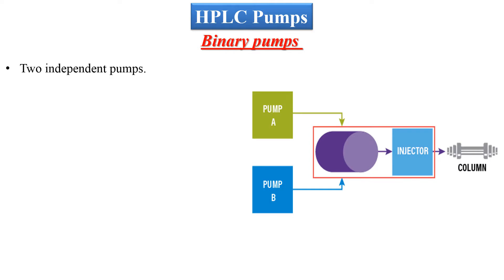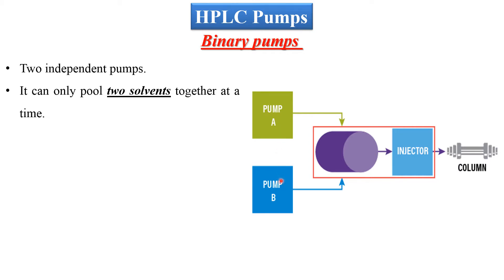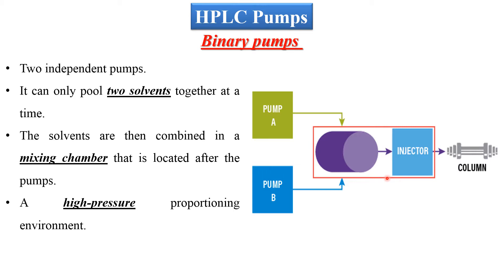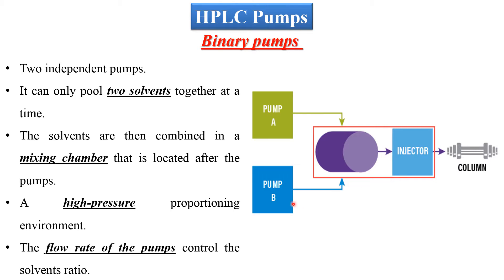As we can see in the design of this binary pump, there are two independent pumps, so it can only deliver two solvents at a time. The solvents are mixed in the mixing chamber before being injected into the column. We can consider this design a high pressure environment, and the flow rate of the two pumps will control the ratio of the solvents delivered into the column.